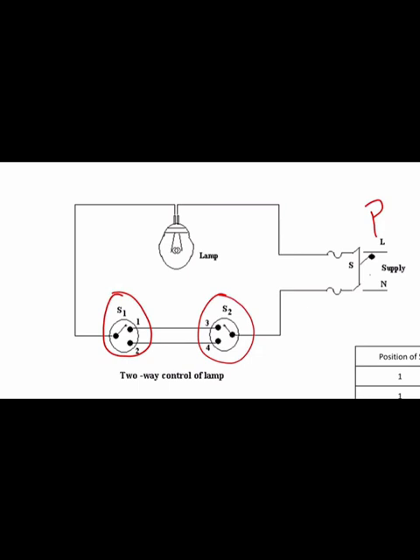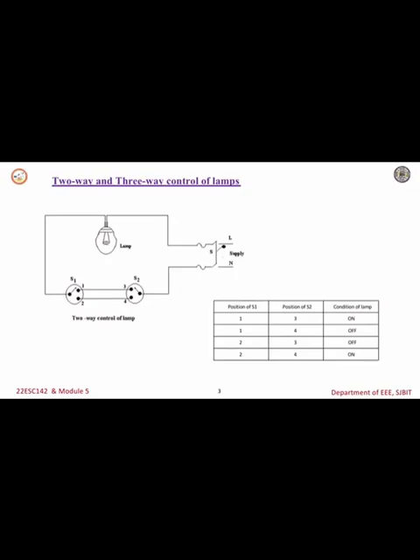Each switch has two terminals. Between the two switches, we make connections with wires: between terminals one and three, and between terminals two and four. When switch S1 is at position one and switch S2 is at position three, the current flows through the lamp, goes to S1 at position one, then through the one-to-three connection, reaching S2 at three and then to neutral — giving a closed path, so the lamp will glow.